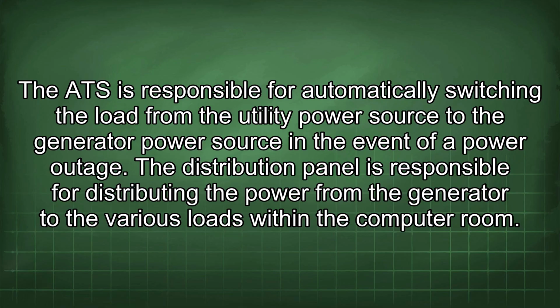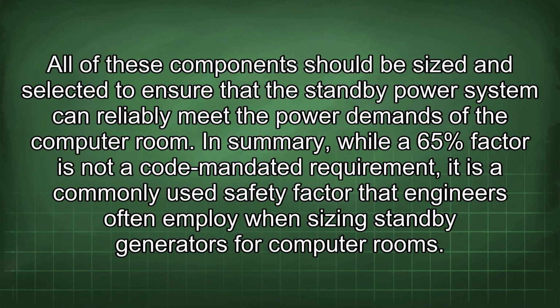The distribution panel is responsible for distributing the power from the generator to the various loads within the computer room. All of these components should be sized and selected to ensure that the standby power system can reliably meet the power demands of the computer room. In summary, while a 65% factor is not a code-mandated requirement, it is a commonly used safety factor that engineers often employ when sizing standby generators for computer rooms.